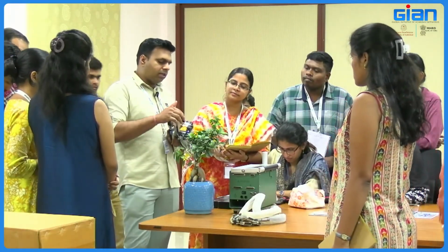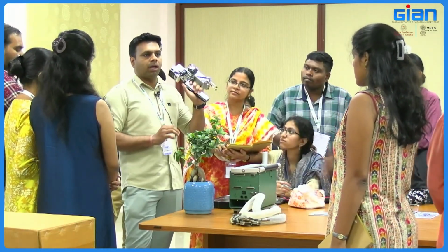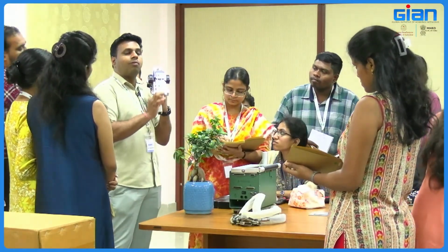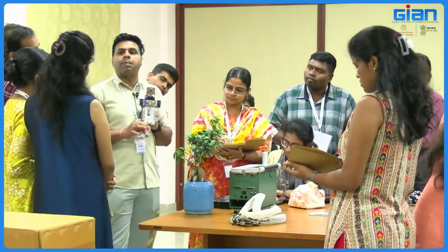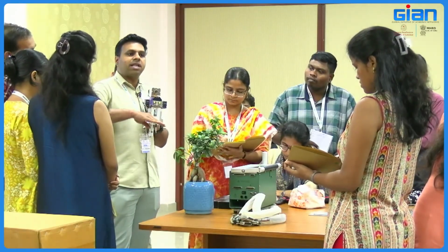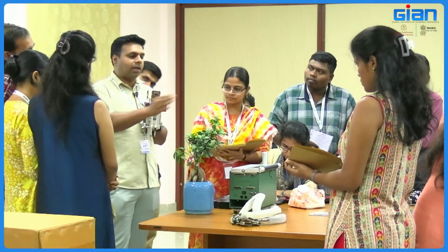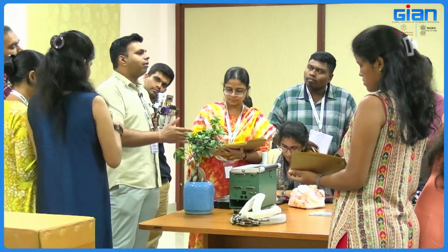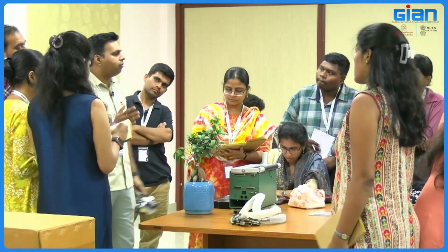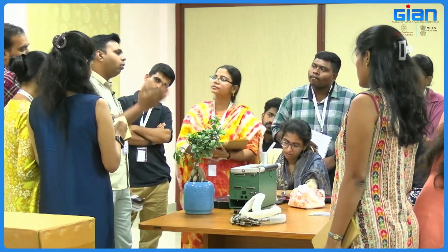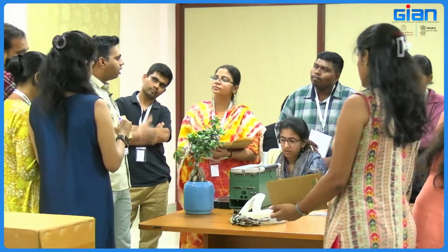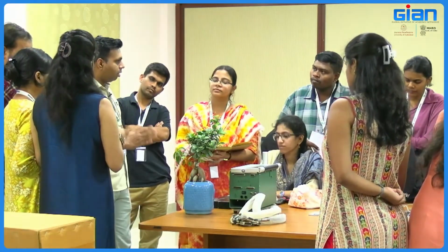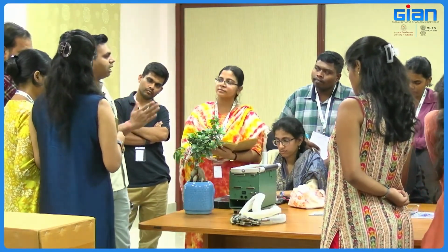So this part is your chamber, the IRGA chamber. Here you see there are two points. One will be for reference and one will be for sample. The reference and sample CO2 difference will be reflected in this machine. Reference will be a constant CO2. Usually if a plant is constantly grown in 1400 or 800 or lower CO2 concentrations, even 200 or 100, that will be the reference CO2 concentration of that plant. Got it? If it is grown continuously from the starting point.